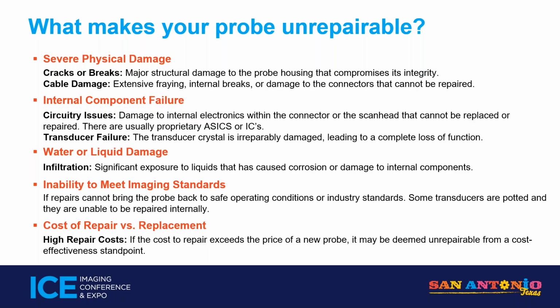Say a probe won't ID. They drop the connector onto the ground, then plug it in anyway, and now it won't ID. It's a fairly common failure on a probe. They try different ports and it still won't ID, try a different probe and it works fine. It's probably an internal component that got damaged.